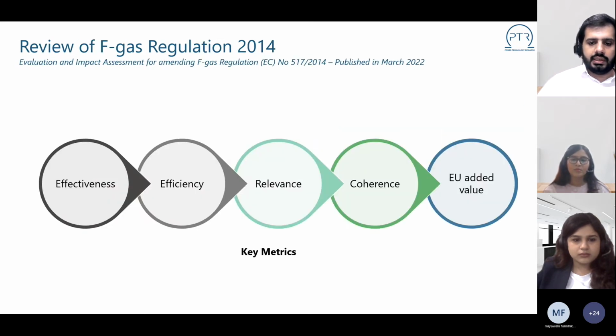With regards to the effectiveness metric, the report concluded that the F-gas regulations have led to a reversal, and the EU market supply of HFCs has declined by 37% in metric tons and 47% in terms of CO2 equivalent from 2015 until 2019. There has also been a clear shift to the use of alternatives with lower global warming potential, including CO2, ammonia, hydrocarbons, and even water, in many types of equipment that traditionally used F-gases.